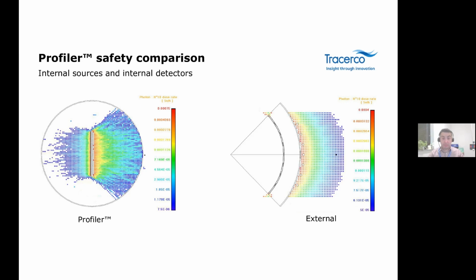So the example shown here has two systems. One is a profiler with the source inside the Tracerco collimator. It's up to 30 source capsules, each containing 1.1 gigabecquerel, 30 millicurie, americium-241 sources. The sources were assumed to be uniformly distributed within the capsules and centrally located in the collimator slots. Whereas on the right-hand side, it's an example of the reduced source inside the standard conventional nucleonic device, made up of just 7 source capsules, each containing, again, a 1.1 gigabecquerel, 30 millicurie source of cesium-137. The sources were assumed to be uniformly distributed within the capsule and centrally located in a source capsule.